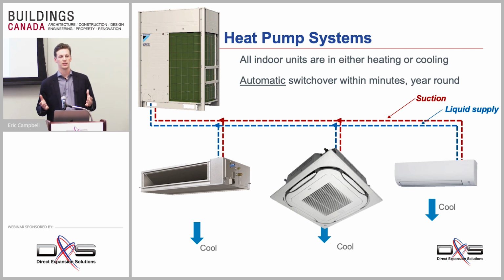We can zone the system or the building so you have similar exposures on a single heat pump system. You could have your north-facing exposure in heating mode and a separate system serving your south-facing exposures in cooling mode. You can do that, but on the single system, it's going to be in one mode of operation.